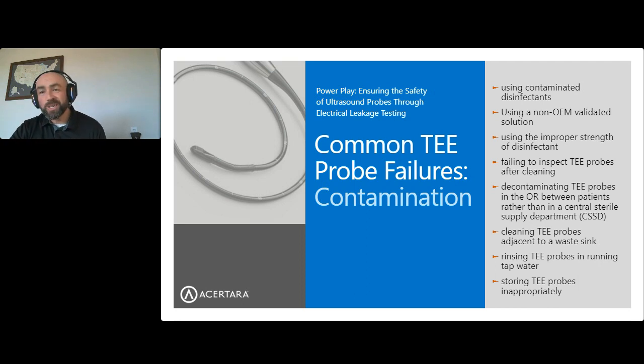Tap water can be a source of additional contamination. So you want to make sure that the water you're using to do your cleaning and rinsing is safe and clean. And then, of course, cleaning probes and then storing them improperly is a big no-no. You're going to end up with damaged probes in that way as well.